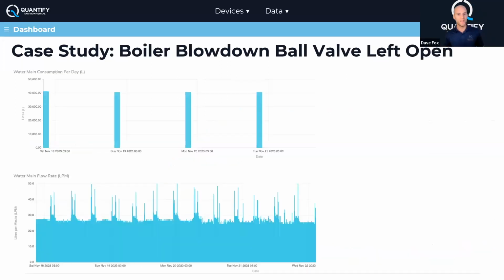Moving on to the next case study. This one seems simpler, just a ball valve that was left open. But the real power of this case study is we've been monitoring this plant for a while, and again it was zero, zero, zero, no baseline flow. Then about 6 weeks ago, this turned on. The facility knew about it, started looking around for it, but couldn't actually identify it. So I went in one evening with this data, now knowing what's going on, went through the facility, and found it was a ball valve controlling the boiler blowdown, which is a common culprit.